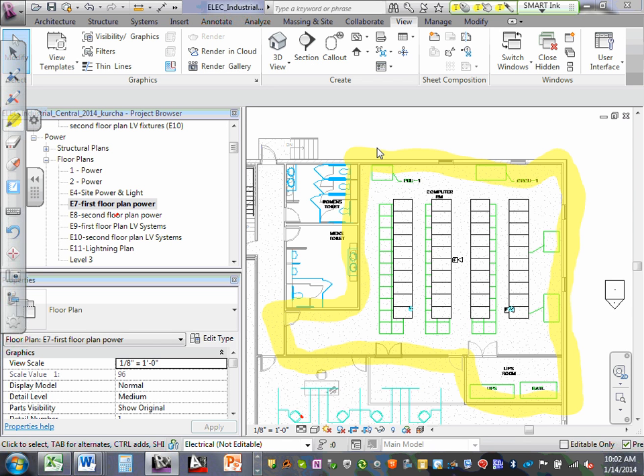But what they are is they're air conditioners that sit on top of the raised floor. And you may have 3 of them down this wall and 3 of them down that wall. What they do is they draw air out of the room, cool it and shove it into the underfloor, into the subfloor. The subfloor is perforated. There's holes drilled in the floor tiles, right? And that air just comes back up through the holes in the floor tiles and recirculates into the room. Boom, goes back down into the CRAC unit and gets shoved under the floor again. So they're air conditioners, just like the window air conditioner in your apartment, only it's used in the computer room, and it's much bigger. And pretty cool stuff. So that unit is going to be causing many air changes per hour inside that room.